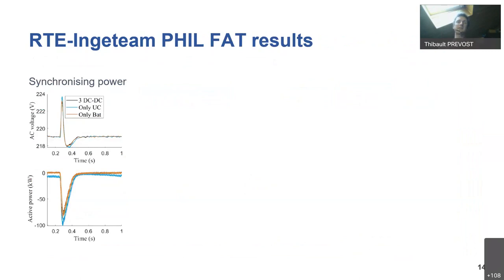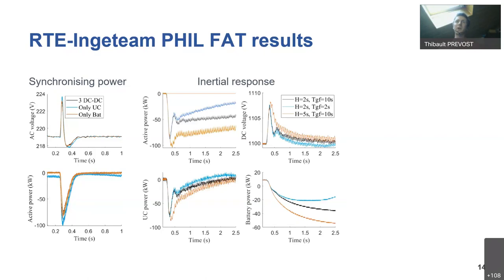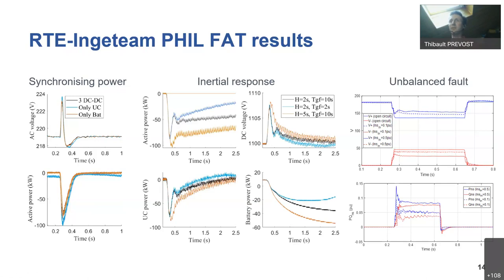So these are, for example, a test in synchronizing power with different modes, or with the three DC-DC converters, which means battery plus ultra caps, or just battery, or just ultra caps. We also have different inertial responses with different emulated inertia, and this TGF, which is in fact the transient grid forming constant, which means that after 2 seconds, for example, the blue one is going back to the set point that was prior to the event. And we have this unbalanced fault where you can keep the voltage balance or the current balance depending on the need you might have locally.